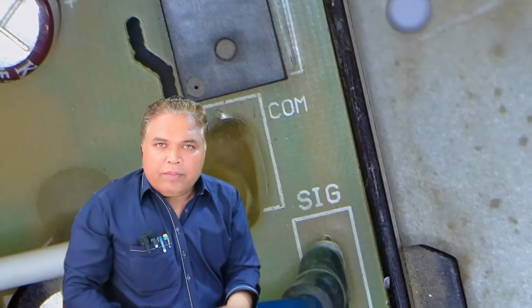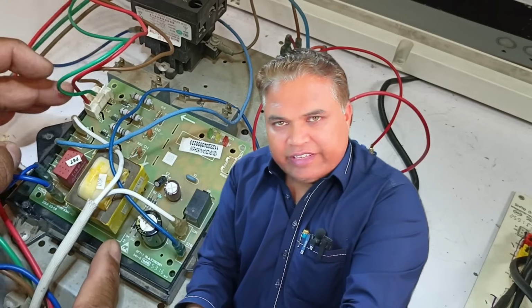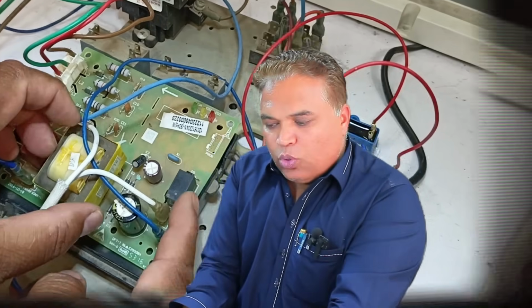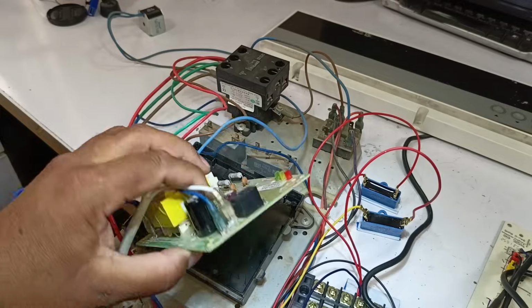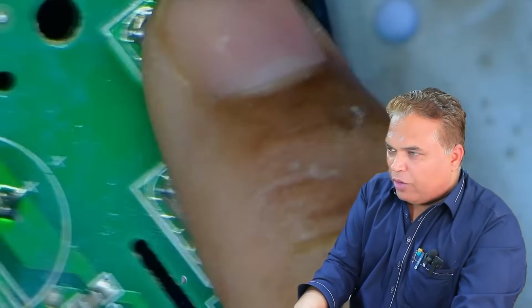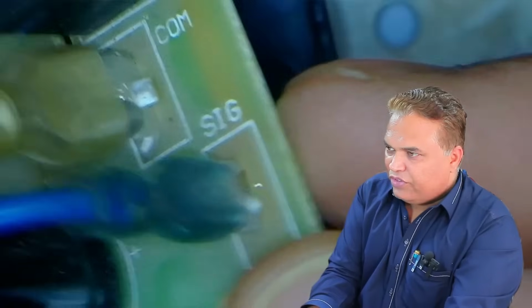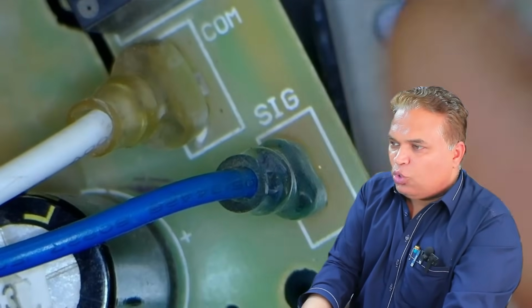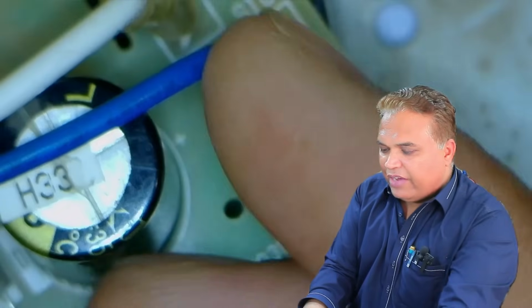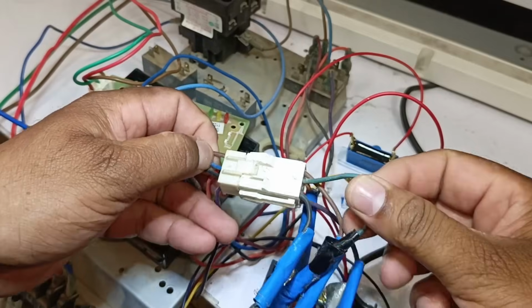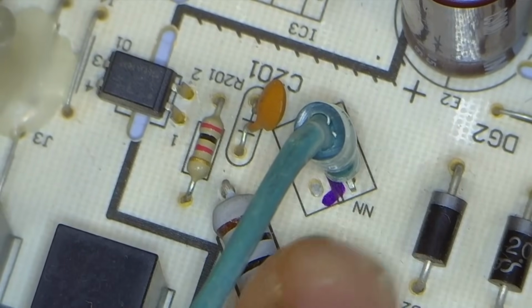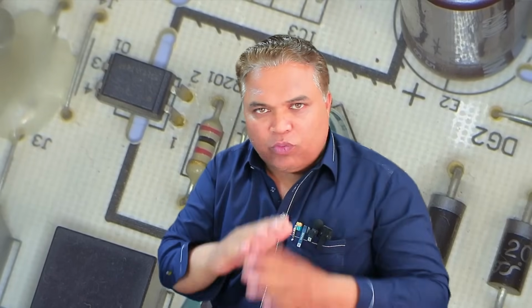When the neutral stands at the common point and we supply power to the outdoor unit, then if the phases are correct and the system is operating properly, this relay RY1 switches internally and makes a connection. When the relay switches, the neutral is shifted from the common point to the signal point. This shifted neutral signal then travels through the wires and enters the connector. From there, it passes through the blue wire into another blue wire that is connected to the double N terminal. In this way, the signal loop is completed.